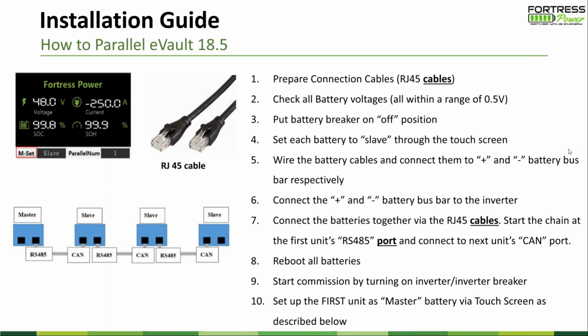Paralleling the eVolt or eFlex system is a little bit more complex. It goes with 10 steps, but don't be afraid of it. It's pretty straightforward. We just want to build up a communication between each battery. So the battery's embedded computer, the batteries will talk to each other with CAN bus. It helps you to monitor the voltage differences. If one battery has a problem, voltage drops so quickly, or they deteriorate differently and so on, the system is going to kick this battery out when you operate the system.